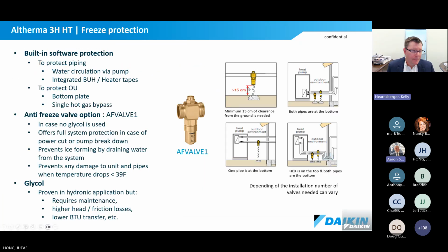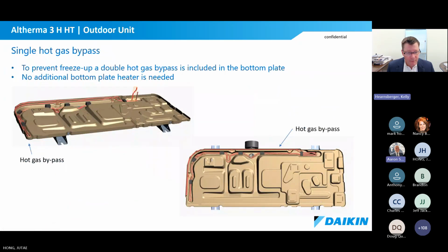A little bit about the drain pan itself. If you're in a northern climate, I mentioned before, these systems were designed uniquely even for northern climates. And so what we do on the drain pan is we pull off some hot gas from the refrigerant circuit, and we bypass that into the drain pan. So we run enough circuit to make sure that we clear that drain pan all the time. So consistently in heating, there are no necessary additional kits or electric penalties for the system. We're just stripping off a little bit of that hot gas bypass and then utilizing that to keep the drain pan clear. Next slide.